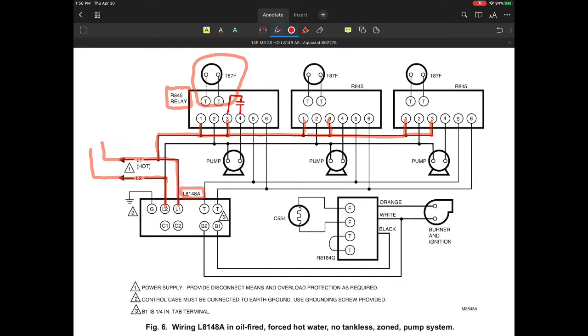Terminal 3 is actually going to a set of relay contacts. So for example, this would then go to, I'm going to draw it this way. That's going to go to a normally open set of contacts. And then usually this will end up going to some sort of normally closed set of contacts or something like that. So that's kind of the way they're doing that. So this one is 3 and 4, primarily from that manner that it's controlling to get the pump circuit. So in any one of these cases, anytime you're dealing with these types of relay systems, you want to really look at their diagram specifically. As you can tell in this diagram, they really don't give you a lot of information. You have to figure it out on your own.